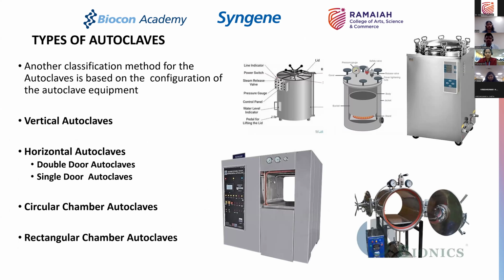It is only from a load perspective, and the fact that when you choose a supplier of an autoclave, you have to be evaluating some of these aspects very, very carefully, saying whether the vendor has sufficient experience in fabrication of a rectangular chamber and sealing those chambers properly, so that you do not have issues.